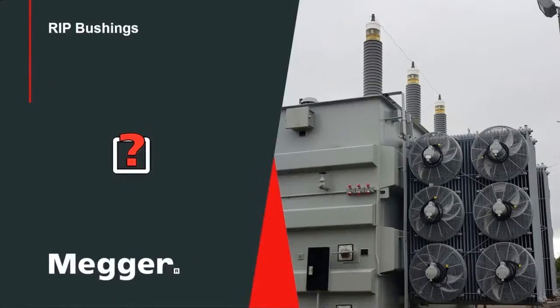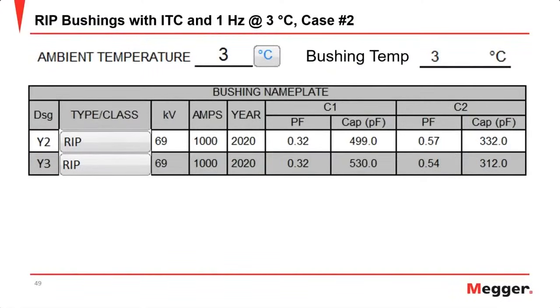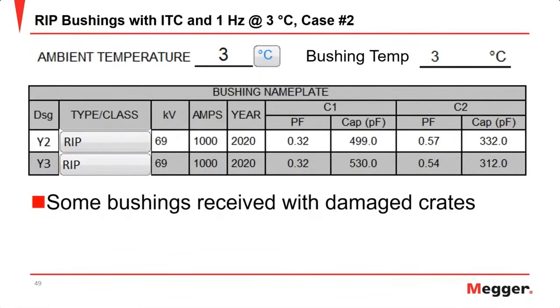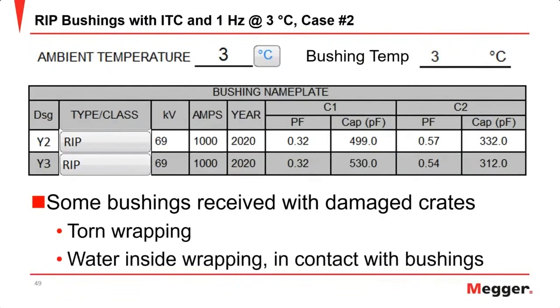Next, we have a case study on some 69 kV RIP bushings. This particular customer, they received some bushings, and they noticed that immediately the crates were damaged. And whenever you notice that your equipment comes in with damaged crates, you get that pit feeling in your stomach that something could be further wrong. Either they're damaged, or in this case, when they opened up the crates, they saw that the wrapper was torn and that there was water inside the wrapping and in contact with the bushings. So immediately alarms are going off. They have to start their commissioning tests.